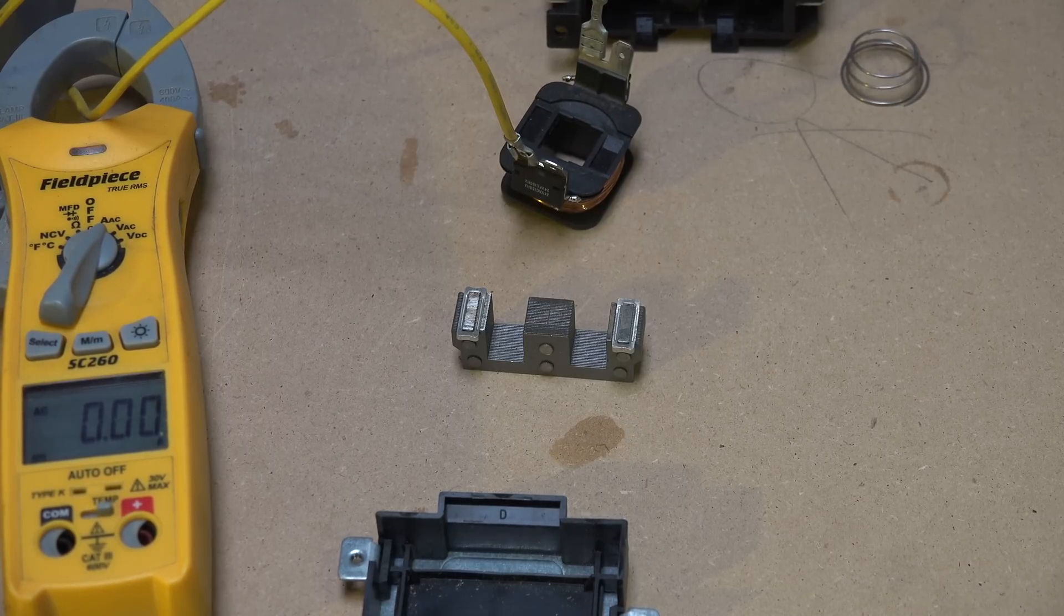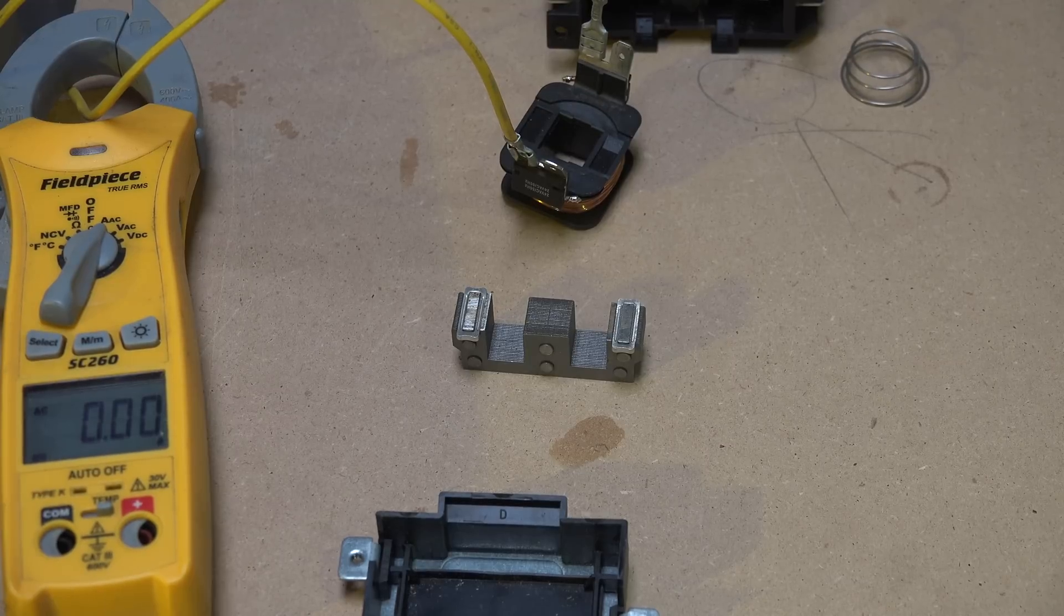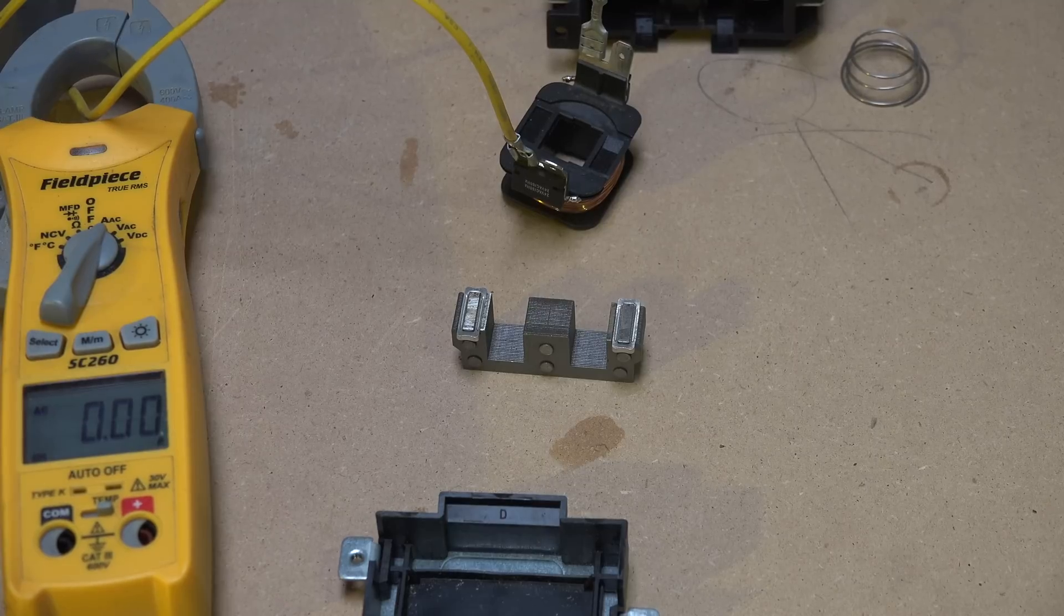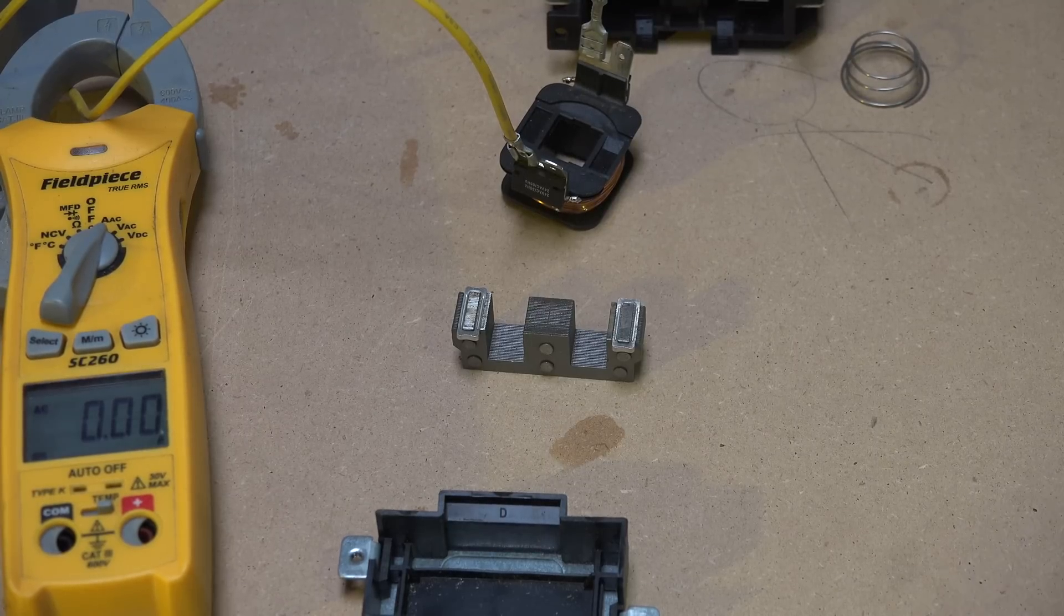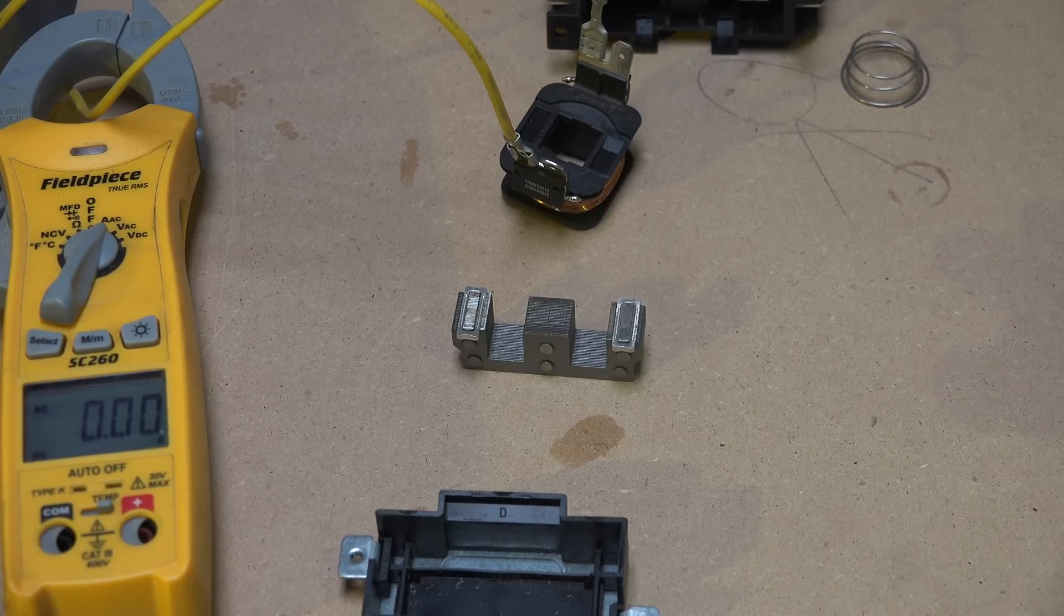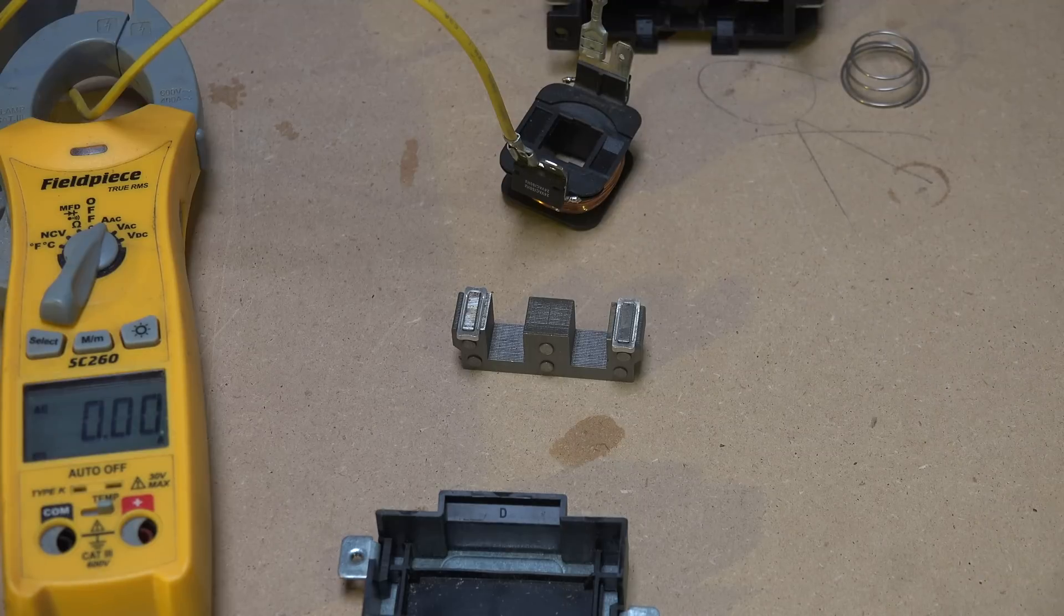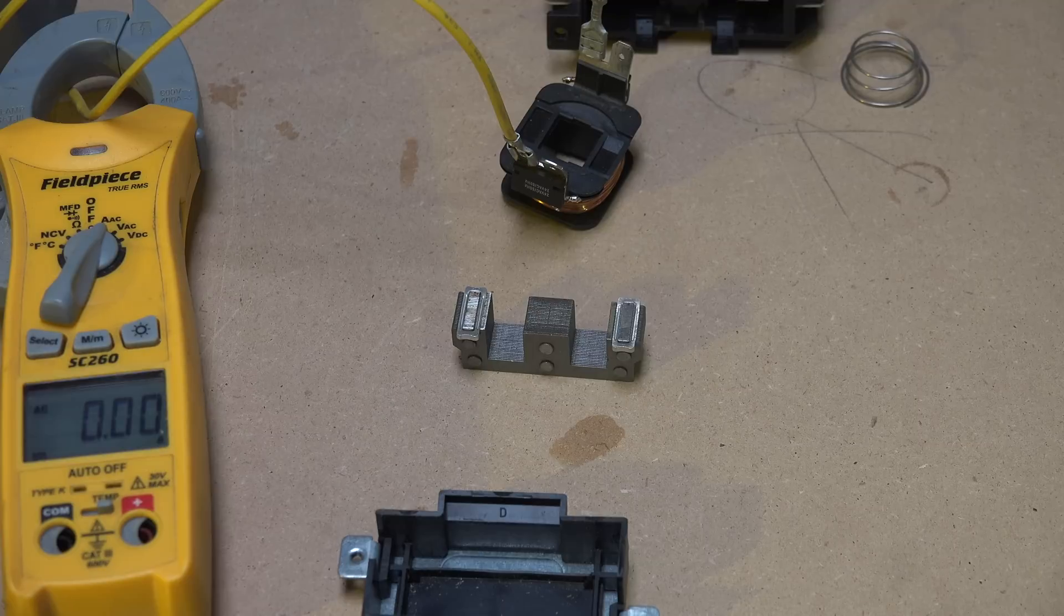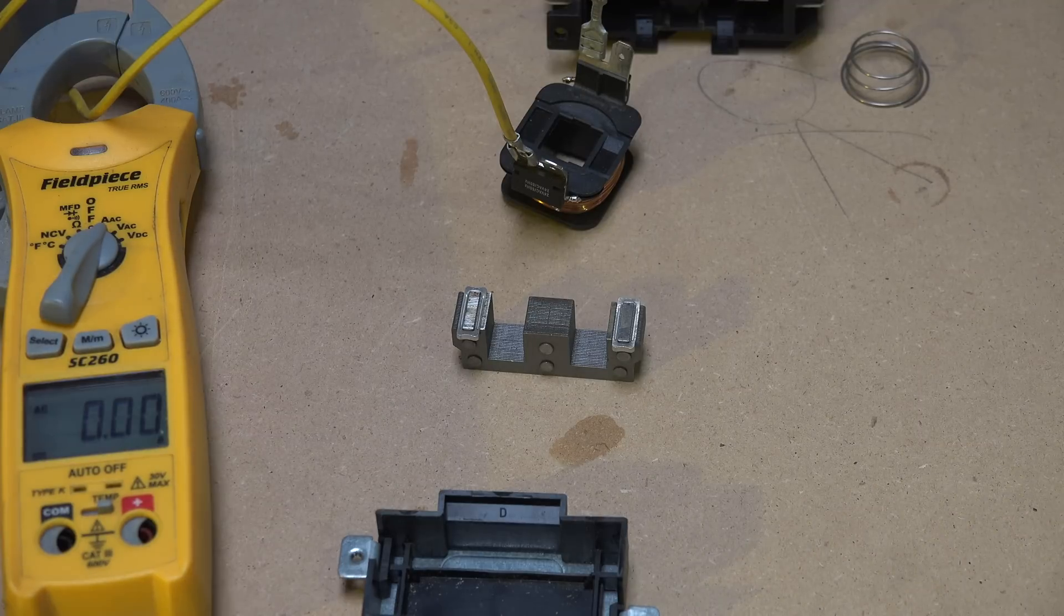And the wires are going through steel conduit and you turn on the breaker and it immediately kicks the breaker off. But you can also hear the wire slap the side of the conduit. It'll make a fairly loud noise. What it's doing there is the magnetic field around the wire has gotten strong enough because of the excessive draw that it is attracted to the steel conduit.